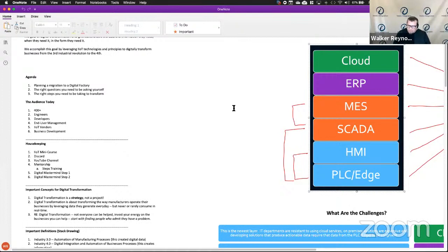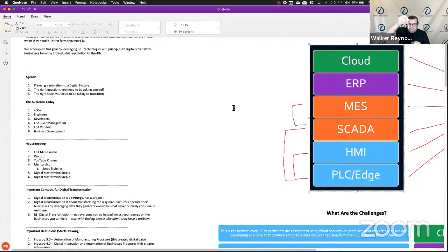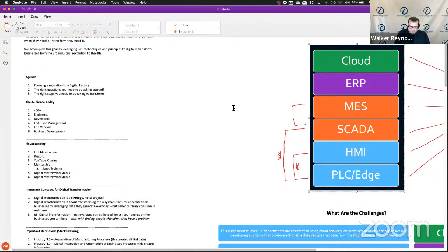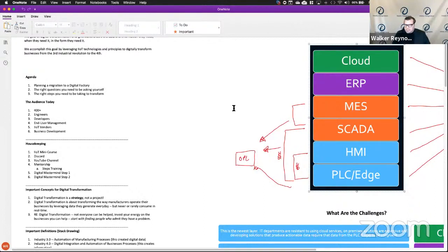During the third industrial revolution, what we started doing is what we call linear integration — the concept that we integrate our process from the plant floor up to the enterprise one step at a time. That started by connecting the PLC to the HMI. That's a discrete connection and it costs money. It also creates two separate data silos — one in the PLC, one in the HMI. Then we did the same integration to the SCADA system, which also costs money. One thing we can do is put an OPC server out here — shout out to Matrikon and Kepware — take our PLC data and put it in the OPC server so both the SCADA and HMI systems get it from OPC. This is where the OPC versus MQTT argument comes from.